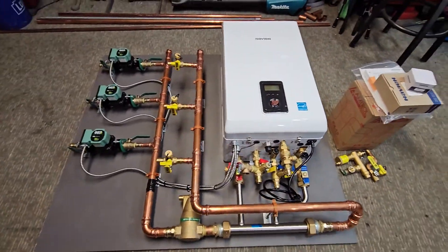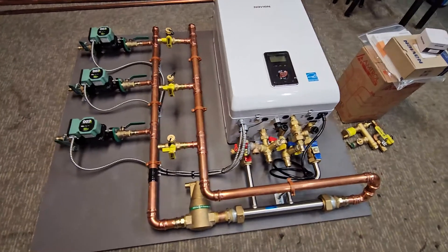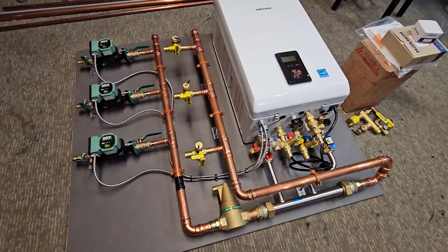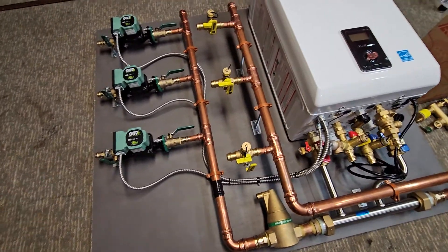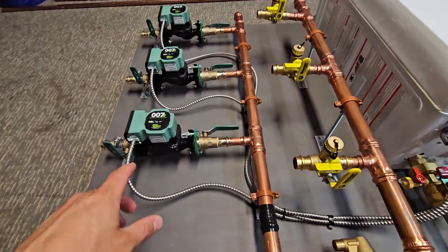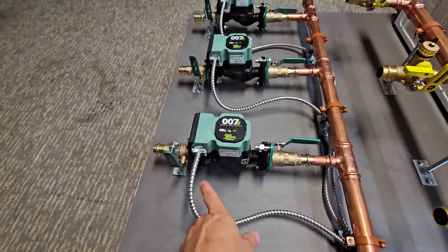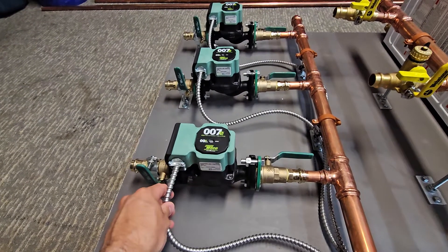What we have here is another three-zone system ready to go — this one's completed, customer is going to be picking it up tomorrow. This is a Navien combi boiler with three zones for baseboard heating. I went with 007E circulators, which are really great for baseboard systems — typically a good size for the amount of head loss you'll find in most baseboard systems.